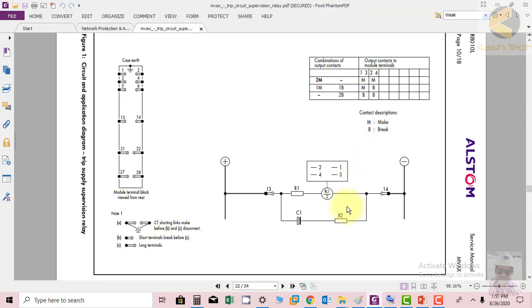And you can see this: if the breaker is closed and you're monitoring in this relay. If the breaker is open, the relay will not monitor whether the trip coil is healthy or failed. So here you can see that they have installed this resistor that we have discussed so far, and this is basically the coil of the relay, and they have installed a capacitor and resistor.